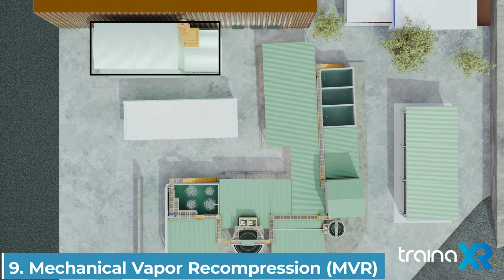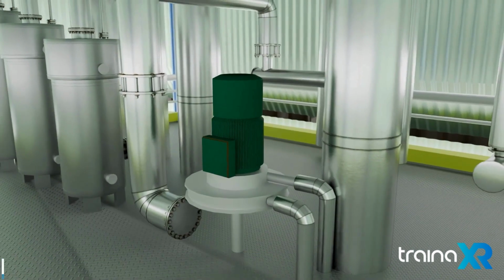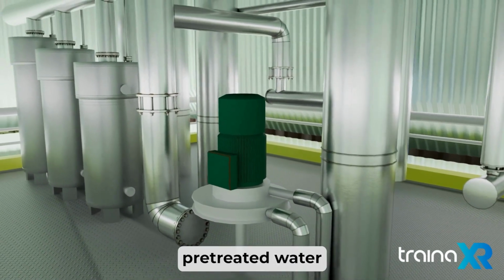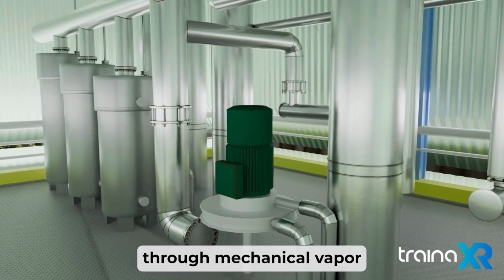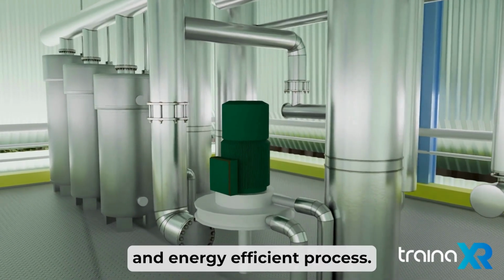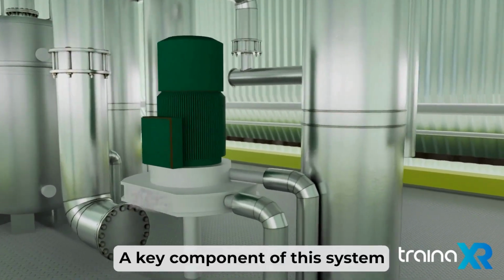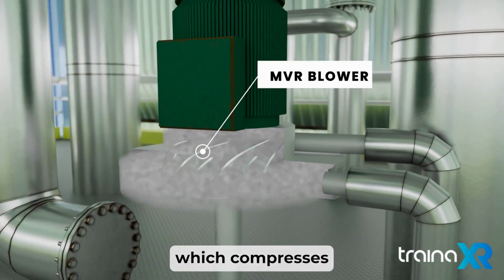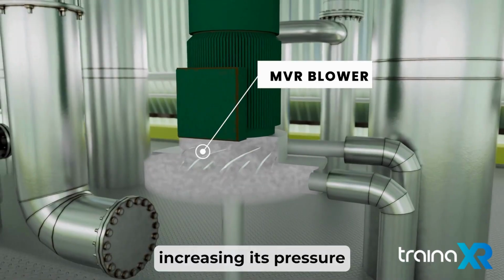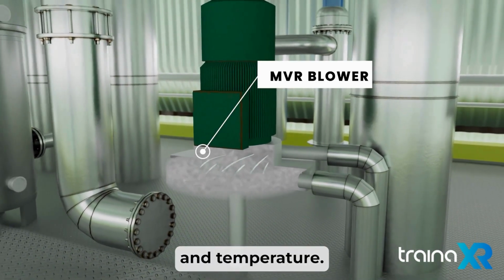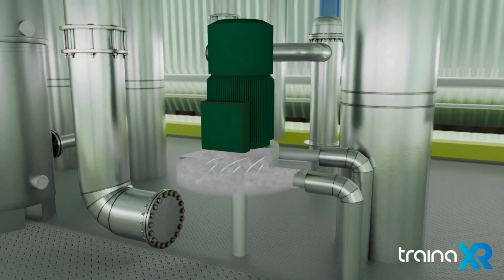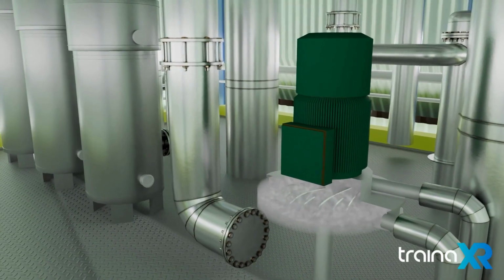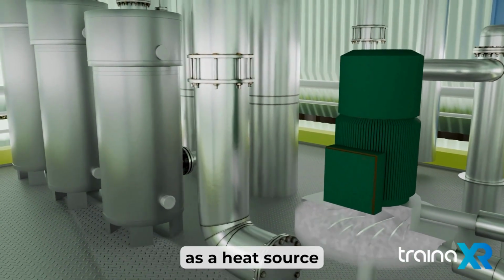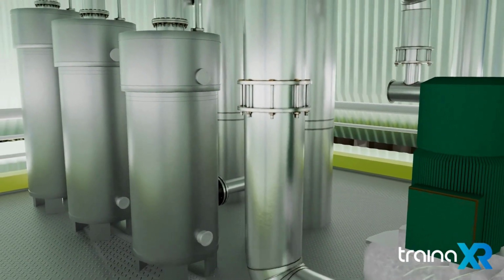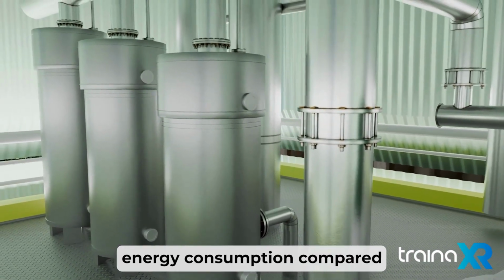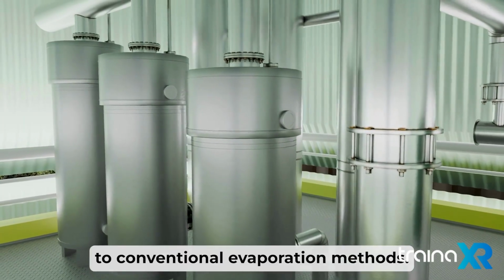Mechanical vapor recompression (MVR). In the MVR system, pre-treated water is evaporated through mechanical vapor recompression, an advanced and energy-efficient process. A key component of this system is the MVR blower, which compresses the extracted vapor, increasing its pressure and temperature. This compressed vapor is reused as a heat source to evaporate more water, significantly reducing the system's energy consumption compared to conventional evaporation methods.